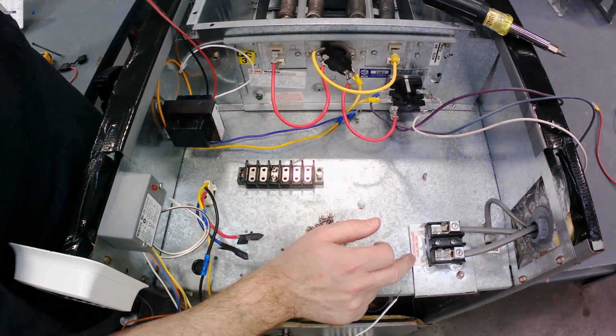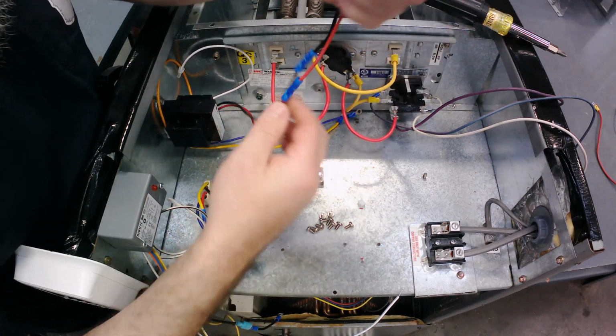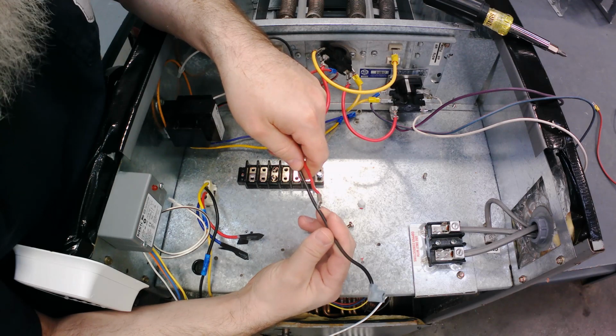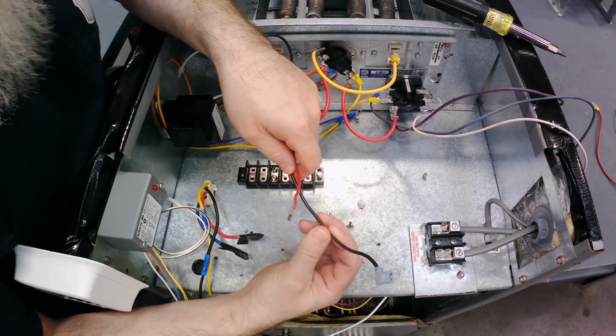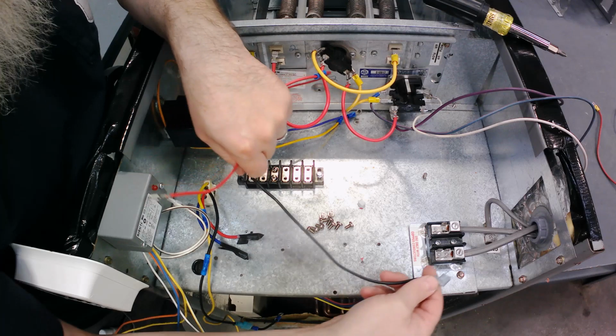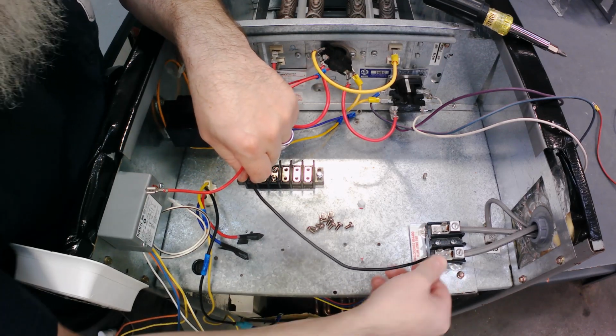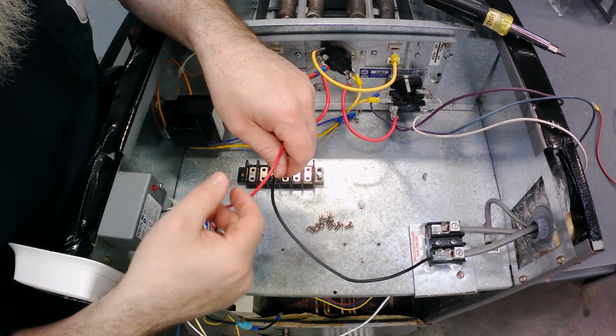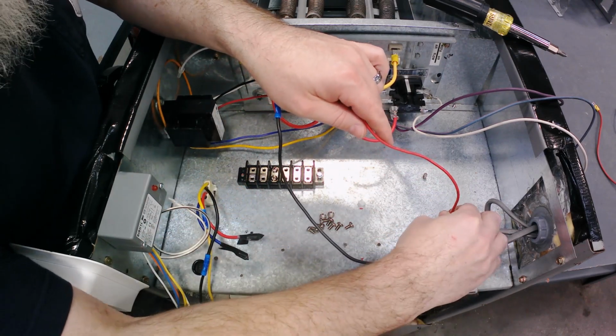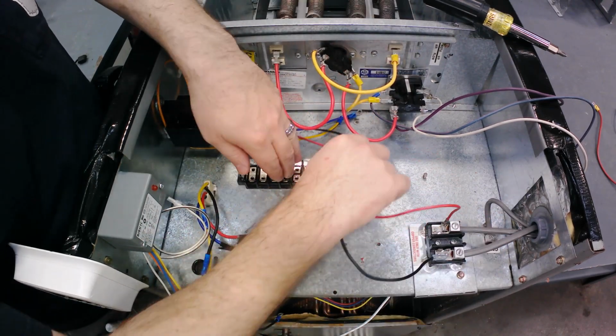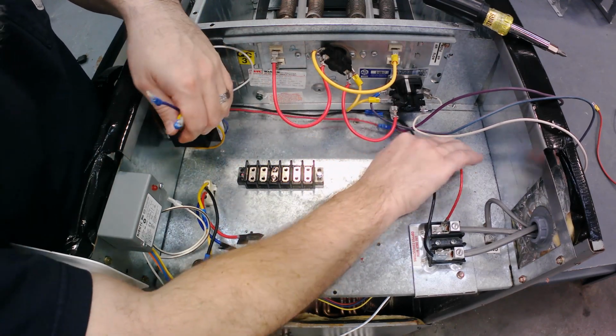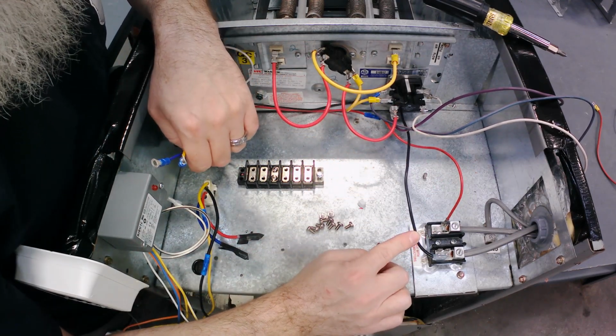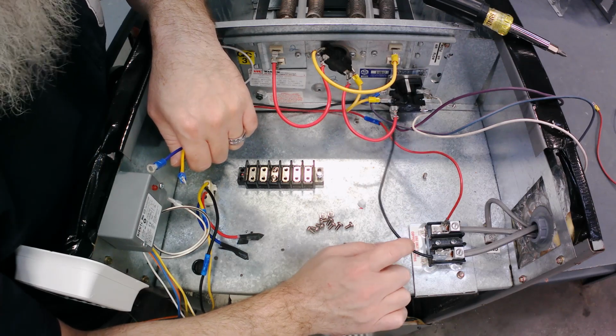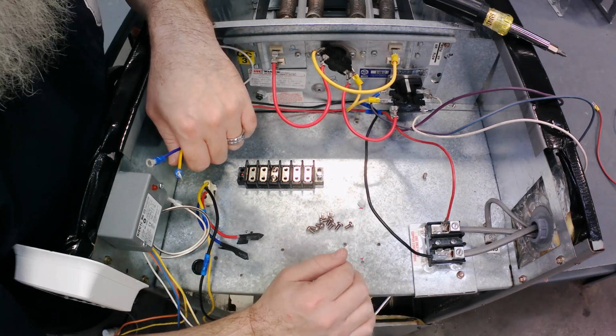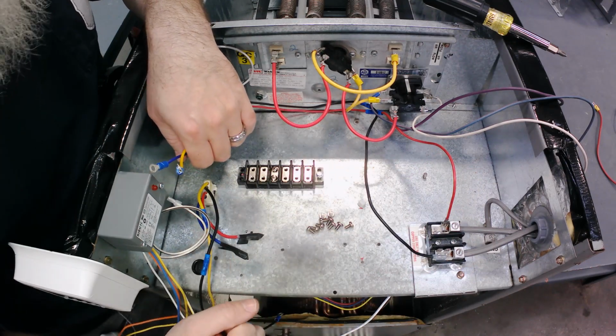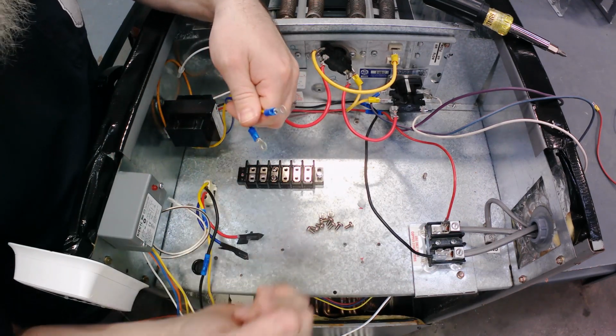So what I'm going to do is power up the transformer - I've got my red and black leads here. The black is common on the transformer, so I'm going to call that my L2 side, and I'm going to follow what they've got there. I'll put that right there on that terminal, and then my red is going to be my tap for 208 volts. So I've established my L1 and L2, and from now on this is my L2 and this one will be my L1. All right, so that's out of the way - that's the primary side of the transformer wired. If I plugged it in now, I'd get 24 volts out of here.